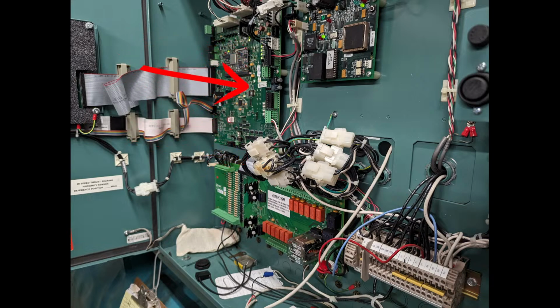Either way, this is your main brain. This processor is actually what runs the entire chiller. These are still inputs and outputs for this module up here, and these are your power rails. This is communication going through your ACC and VSD. Up here are your sensors: temperature sensors, transducers, flow sensors. All of that goes through here, but those are very light loads, pilot duty devices, so they're not putting any major stress on the circuitry for the main micro board.